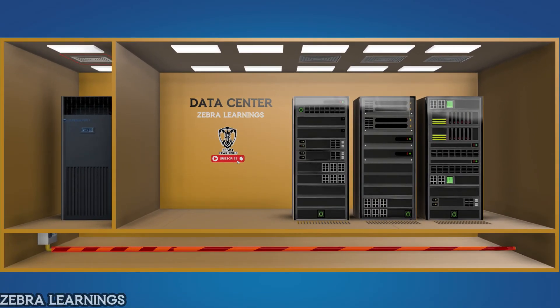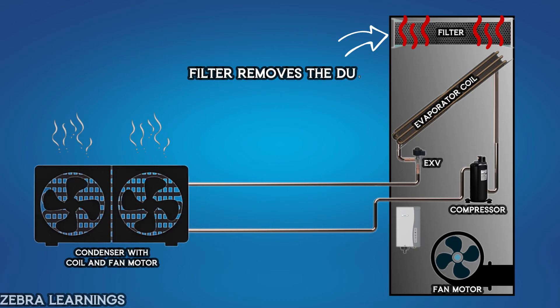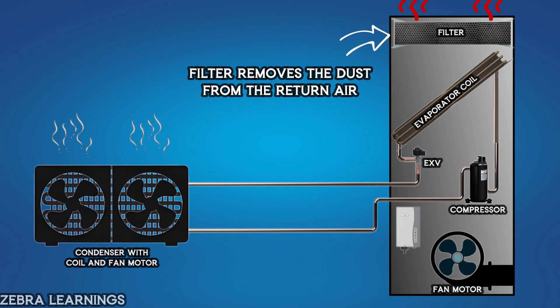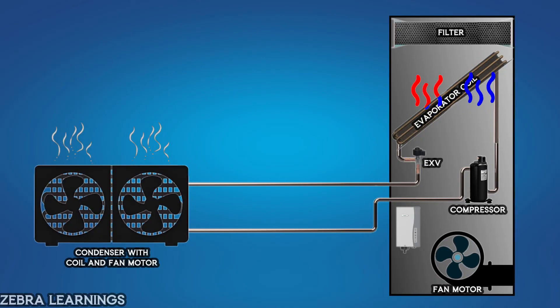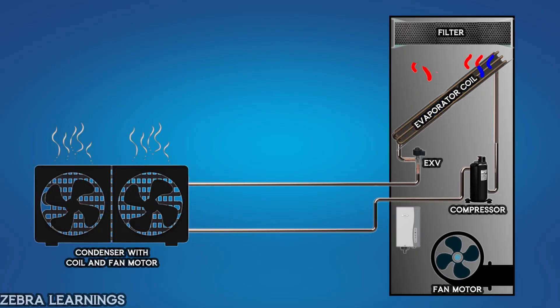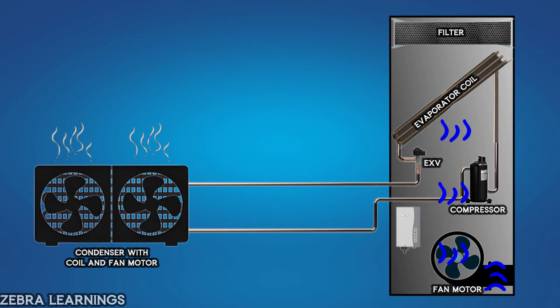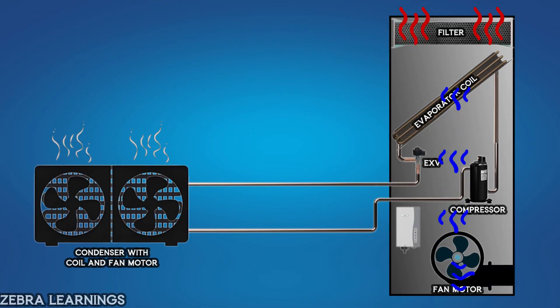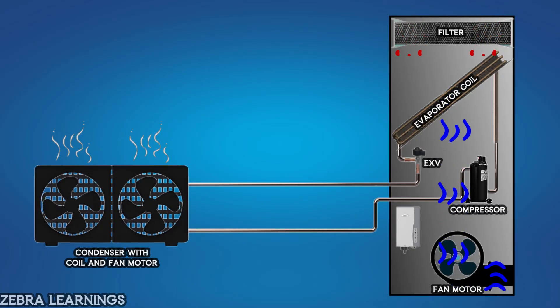Water leak sensors are installed at the bottom of the data center to detect any water leaks. If a leak is detected, an alarm will immediately notify us. In a data center, the air drawn into the PAC through the return duct first passes through a filter to remove dust and other contaminants. Next, the filtered air is directed through the evaporator coil, where it is cooled by the refrigerant circulating within the coil. An evaporator fan motor then drives the cooled air through the supply duct, delivering it back to the data center. This process of air filtration, cooling, and distribution is continuous, ensuring that the data center maintains a cool and controlled environment.